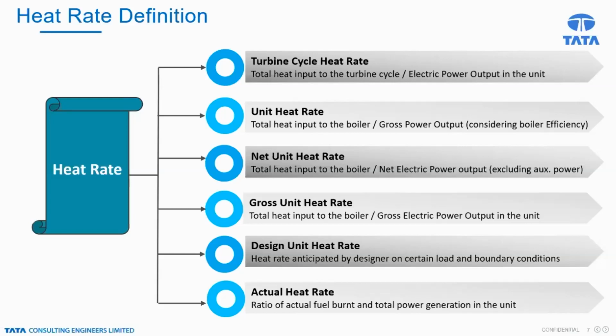Then another way of defining is net heat rate versus gross heat rate. What is the difference? If you want the net heat rate, we have to take the net electric power excluding the auxiliary power. And if you are talking about the gross heat rate, we should take the gross electric power at the generator terminal. So that is the gross heat rate.